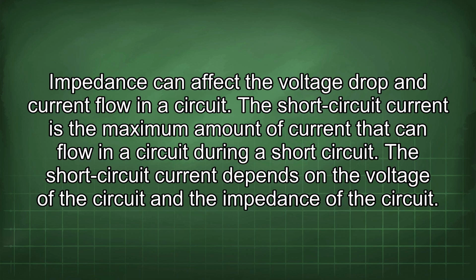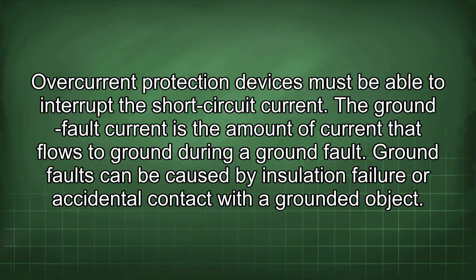The short circuit current is the maximum amount of current that can flow in a circuit during a short circuit. The short circuit current depends on the voltage of the circuit and the impedance of the circuit. Overcurrent protection devices must be able to interrupt the short circuit current.